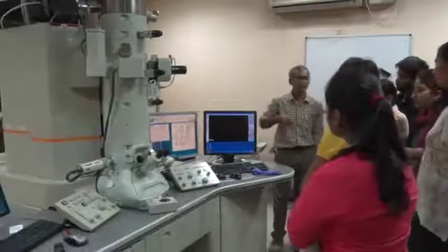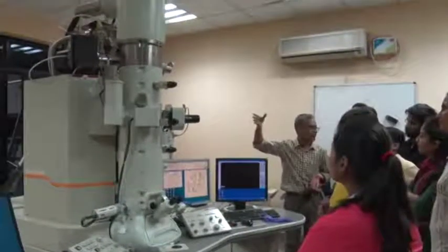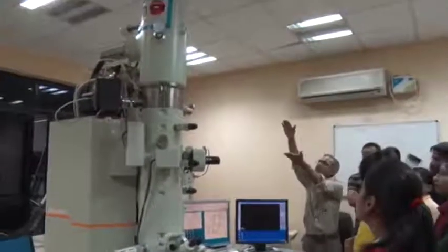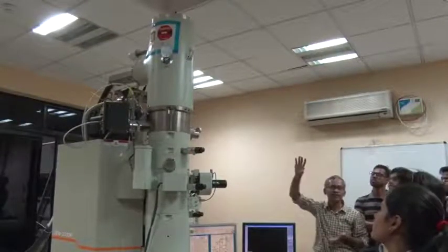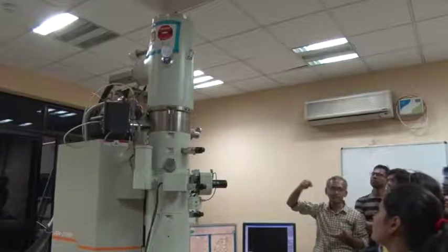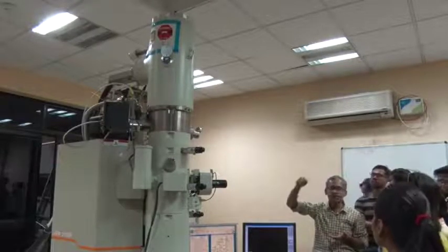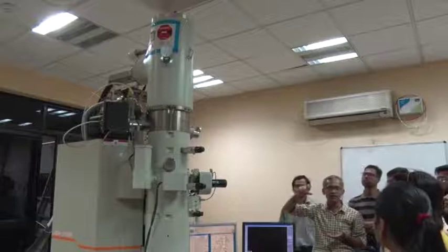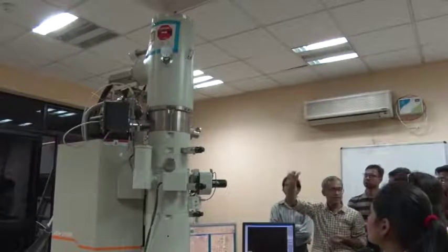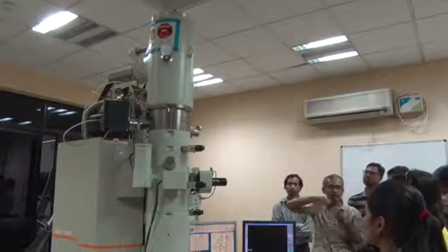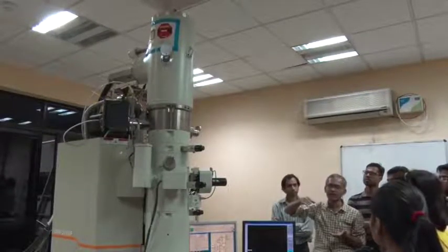And we will proceed with understanding the microscope. So that top unit which you see, the 2 feet long unit, that is the gun part. It will consist of a filament, in this case a Schottky field emission filament.